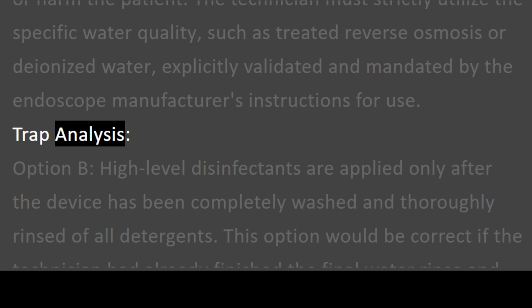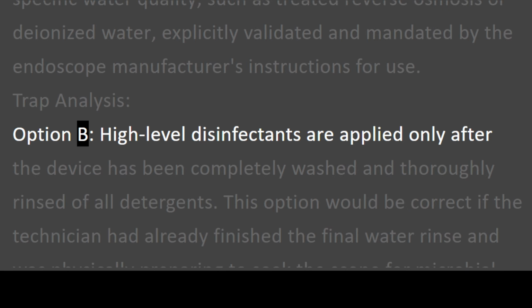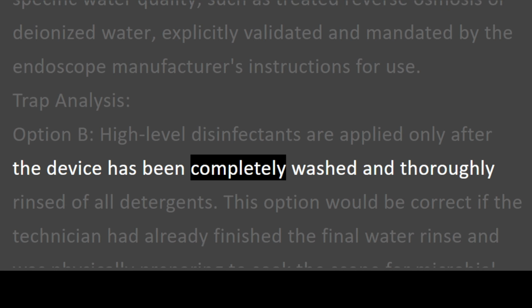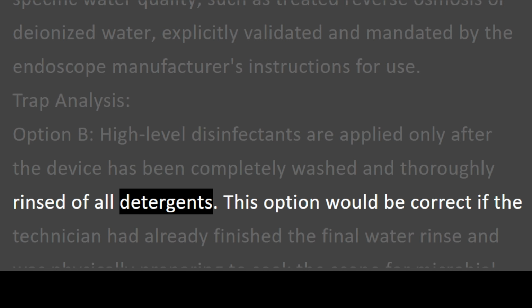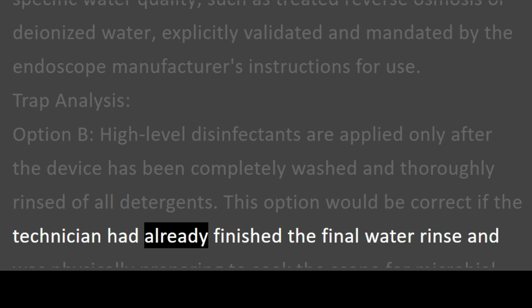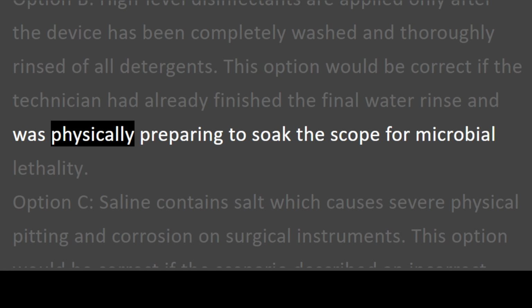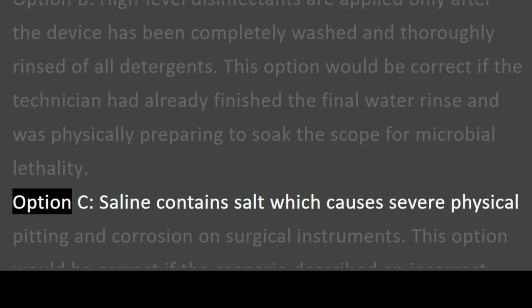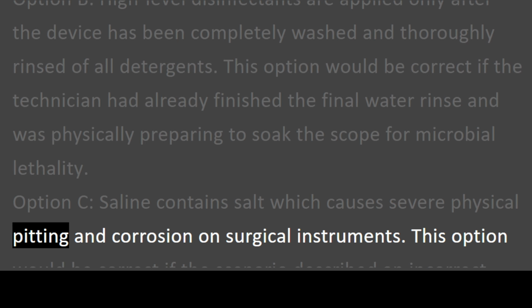Trap analysis. Option B. High-level disinfectants are applied only after the device has been completely washed and thoroughly rinsed of all detergents. This option would be correct if the technician had already finished the final water rinse and was physically preparing to soak the scope for microbial lethality. Option C. Saline contains salt which causes severe physical pitting and corrosion on surgical instruments.